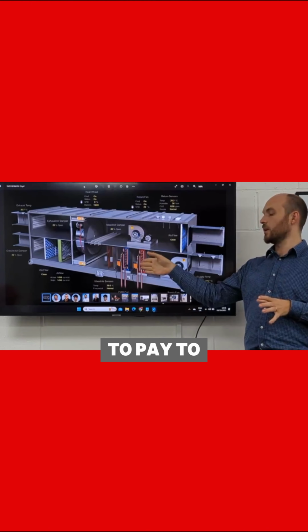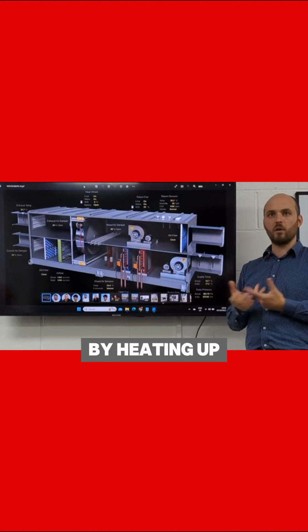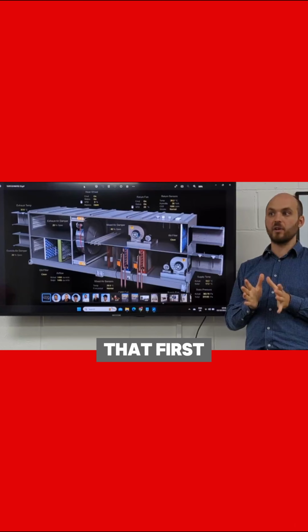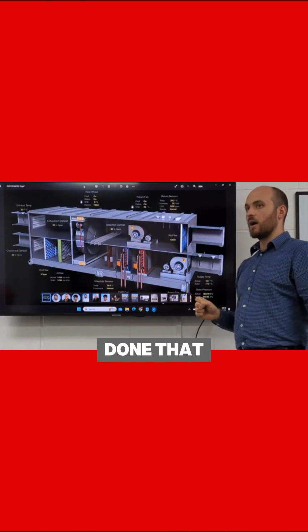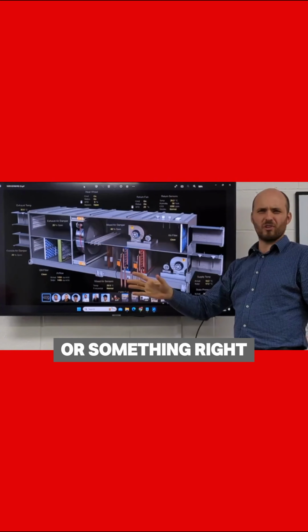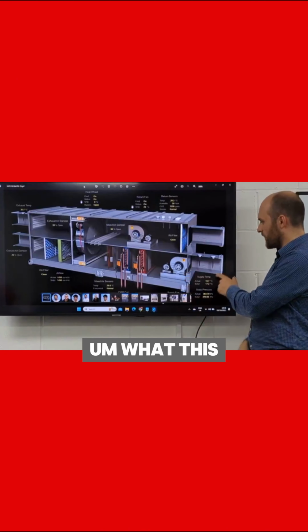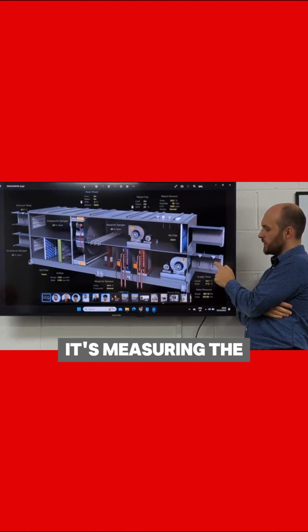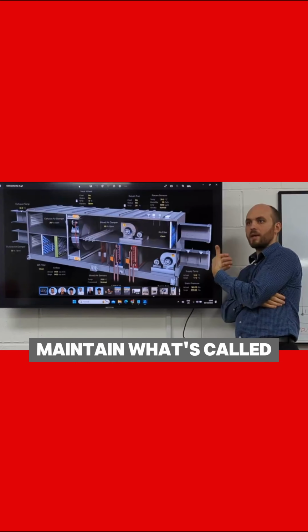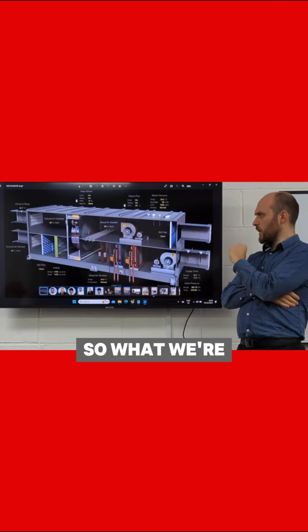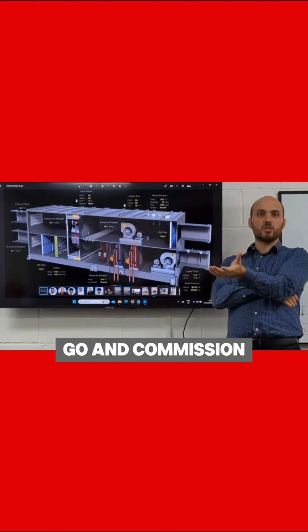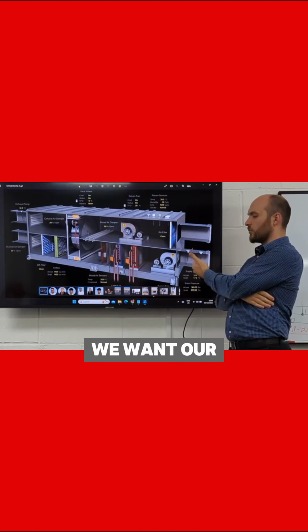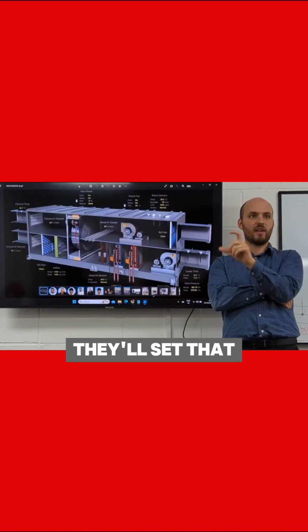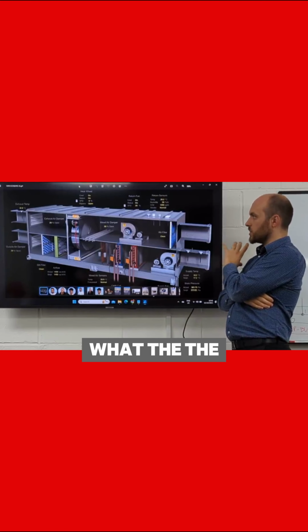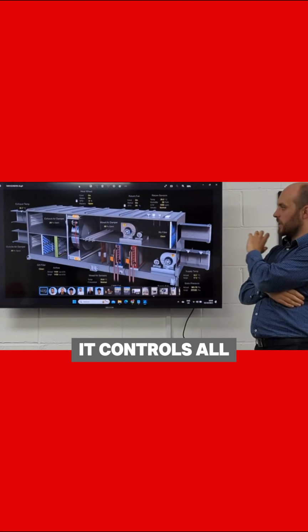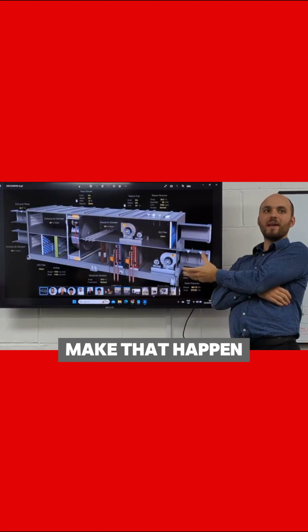Before we have to pay to heat up water mechanically, by heating up a boiler or something like that, we'll be doing that first. So the next stage, once we've done that, we might find that we only recover 4 degrees or something, right? What this temperature sensor is doing is measuring the value that comes out in order to maintain what's called a set point. So what we're going to do on our control system when the guys go and commission them is they're going to say, right, we want our supply air to be 22 degrees. They'll set that up on the screen. What the control panel then does is it controls all these components in order to make that happen.